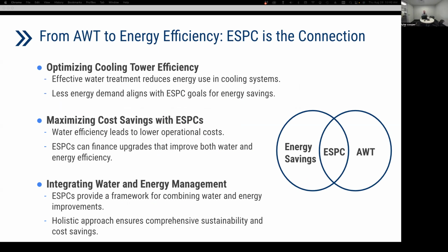So in terms of alternative water treatment technologies, within all these, we're seeing water savings across the board. And if they're leveraged right, you can also see energy savings as well. So ESPCs provide a good delivery mechanism to implement these technologies and capture those savings along the way. Effective water treatment reduces energy use in the cooling systems. If we are lowering the scale, we have seen increased performance in chillers as a result of the cleaner condensing water being sent to those chillers. So if you are able to measure that, that's an additional cost leverage that you can get within that ESPC contract.